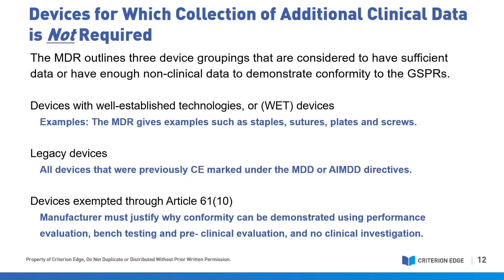How do the clinical evaluation reports differ for a WET device? Well-established technology is mentioned in Article 52 of the EU MDR, but it's not very clearly defined. Luckily, MDCG 2020-6 Section 1.2 adds a little more clarity and has defined WET as medical devices meeting all of these four criteria. They're relatively simple, common, and stable in design with very little evolution. The generic device group they fall into has proven safety outcomes and has not been associated with any major safety issues in the past.